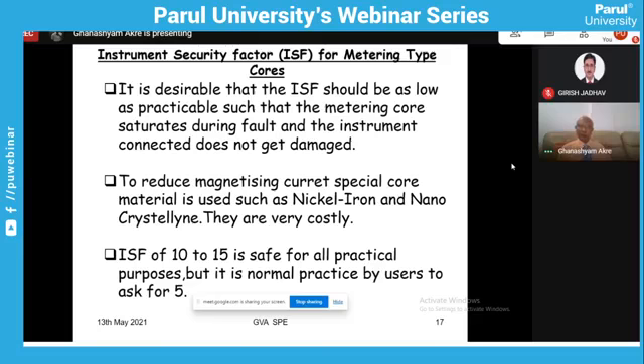So if instead of 5, the current is increased to 10, it is not going to carry 9 amperes. It will be saturated and it will possibly be carrying 5 or 6 amperes depending upon the characteristic of the core. That is how the current will be limited in the secondary circuit, that is the meters and relays, and they will be protected.